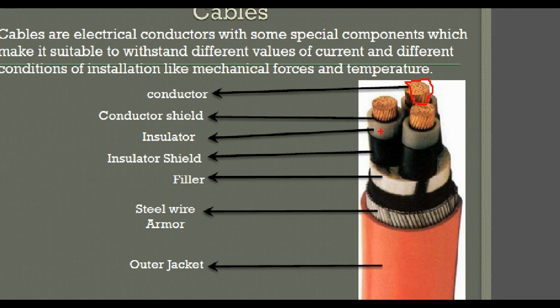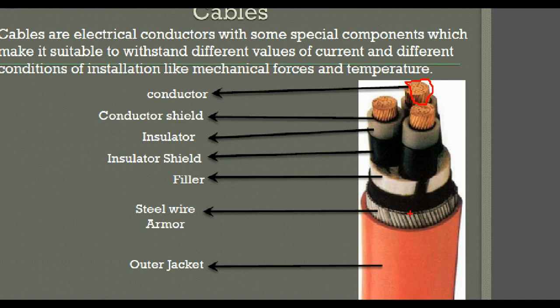The conductor is covered with a conductor shield, which is made from a semiconductor material. Then comes the insulator, which is normally made from PVC or XLPE. This is covered with an insulator shield, also a semiconductor material. Then the filler, which fills the space between the cores of the cable. Finally, the steel wire armor protects the cable from mechanical stress, and the outer jacket covers all the components of the cable.